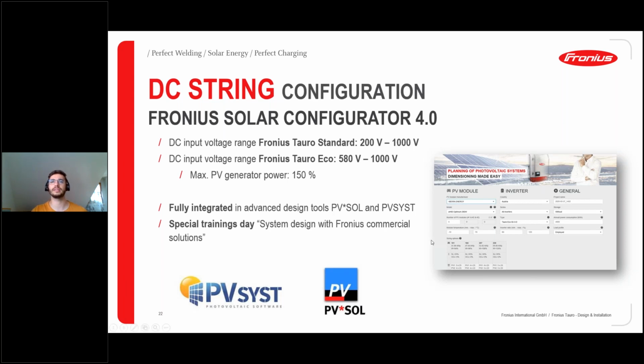Here's a screenshot on the right-hand side. The main focus of this tool is to make sure you don't exceed any limits - for example the 1000 volts, or any current or power limits on the inverter. In just a few steps you can make sure not to exceed any limits, and then go on to more integrated tools, for example PV-Syst and PV-Sol, where you get even more detailed answers like yield forecast and so on, which customers quite commonly ask for.